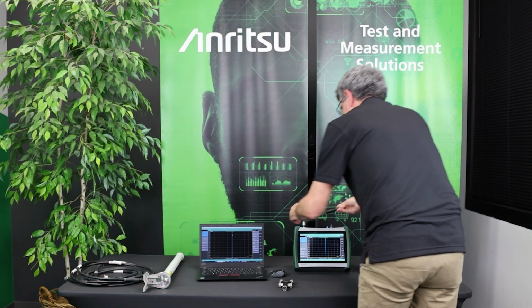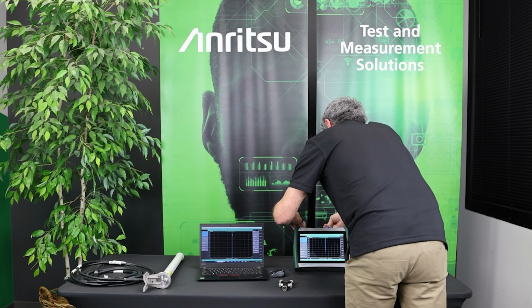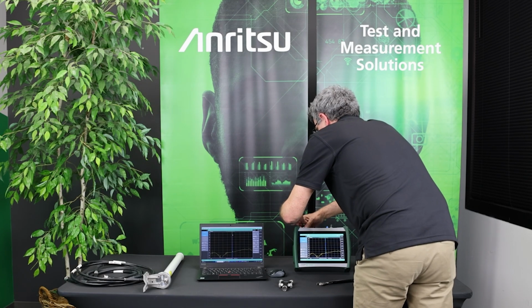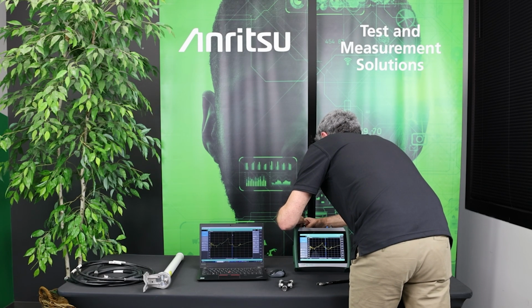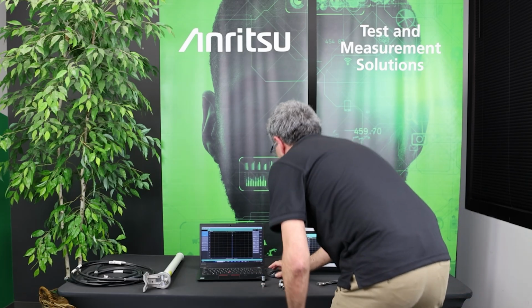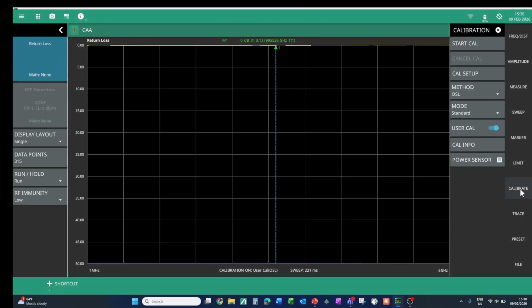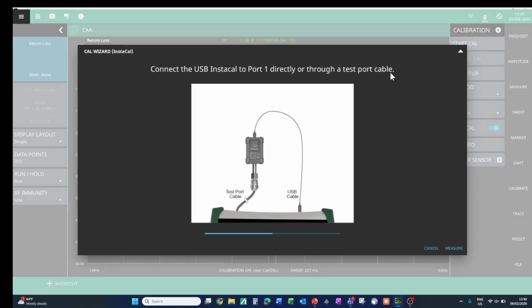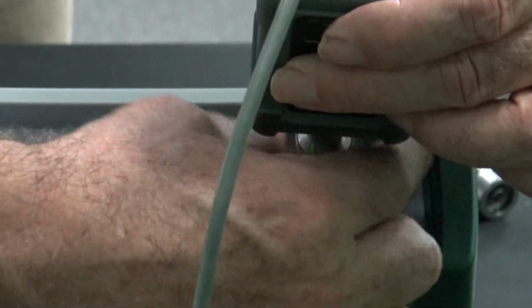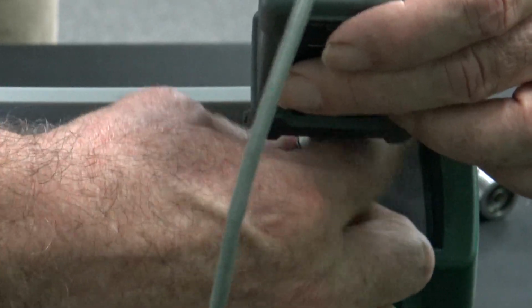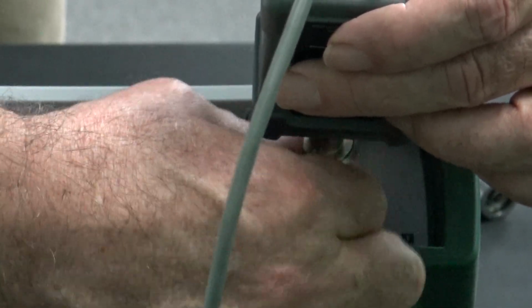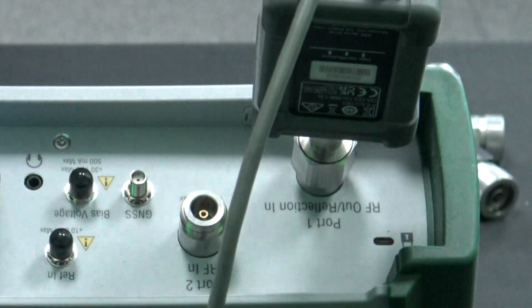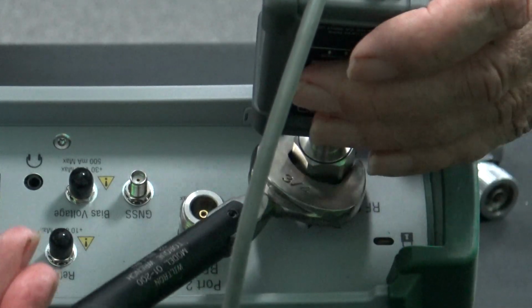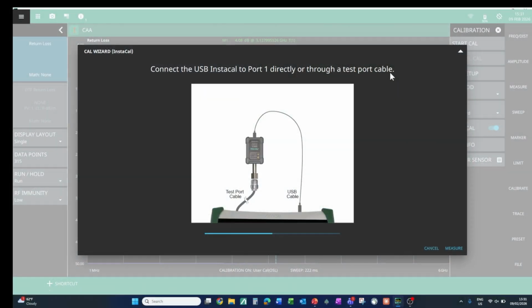The final calibration that we're going to do is with the InstaCal. So now I go back into the calibration menu, go to Method, and I select InstaCal Open Short Load, Start Calibration, and it shows me to connect the InstaCal to the test port. So let me just do that up. Now in this instance, I will only have to make the connection once because this will switch between the open, short and load in the module under control of the USB cable.